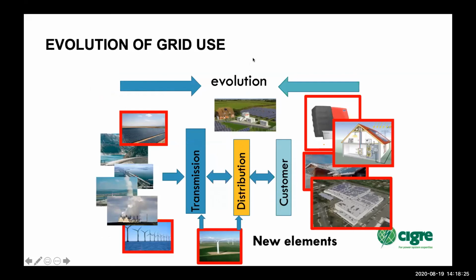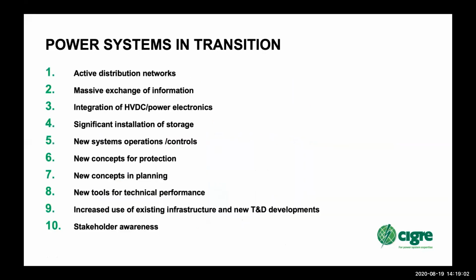Basically we can all understand that in the past we had generation on one side, customer on the other side, power flow was in one direction. Now we get power flow coming in any direction, and generation is inserted at any point. With large rooftop PVs, you can get power flowing from the customer into the transmission network and through the transformers, which creates problems, because originally when they were installed, power flow was normally from high voltage to medium or low voltage, rather than the other way around.